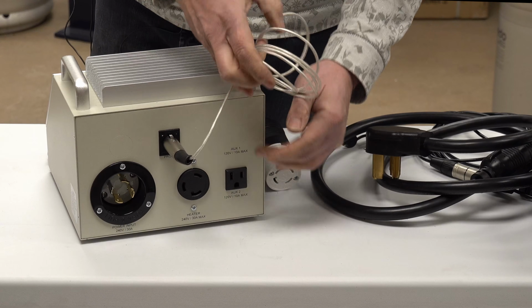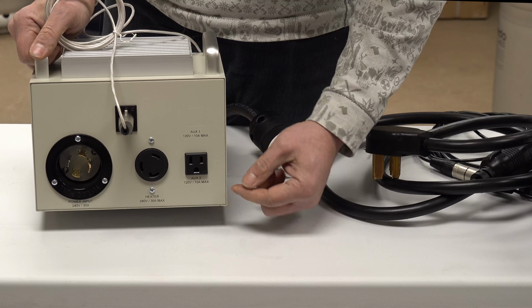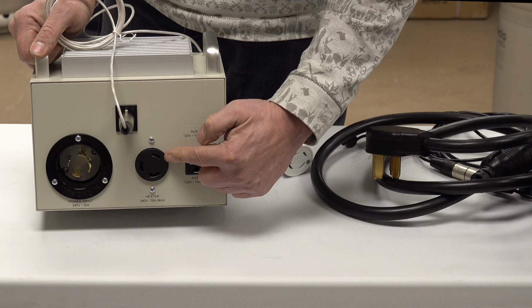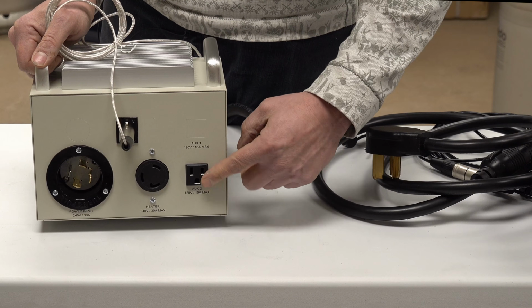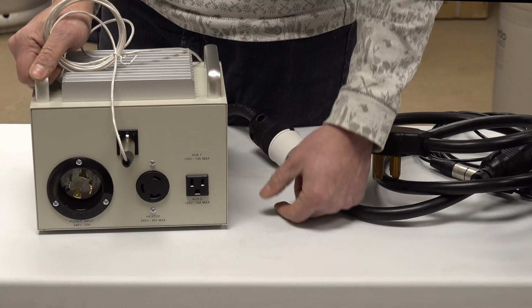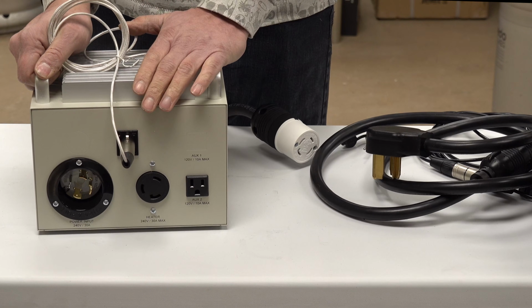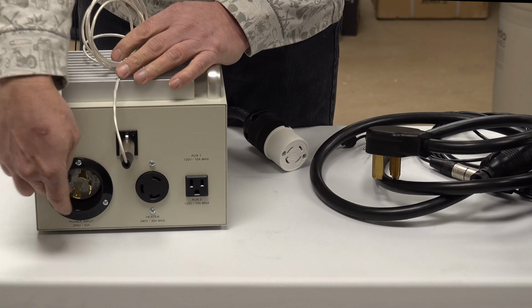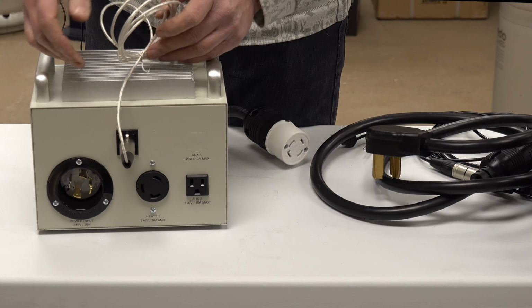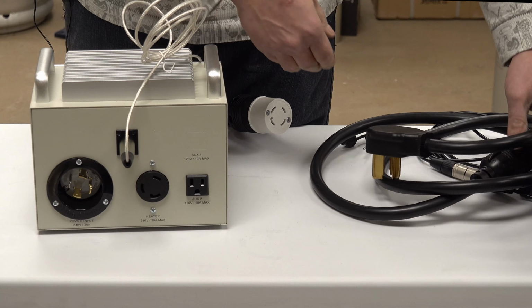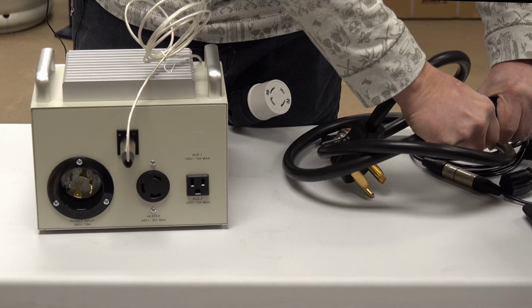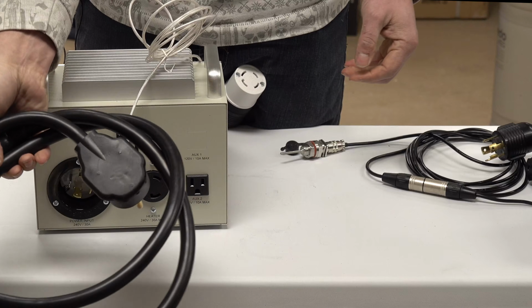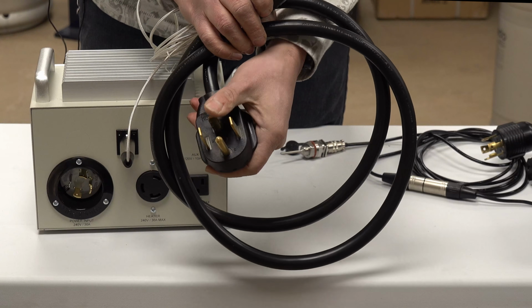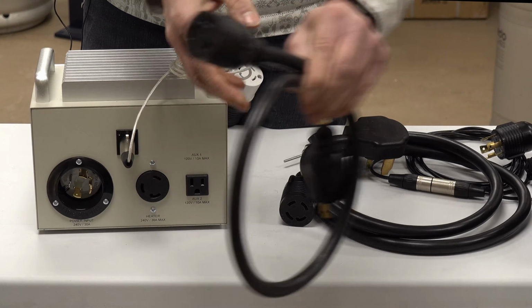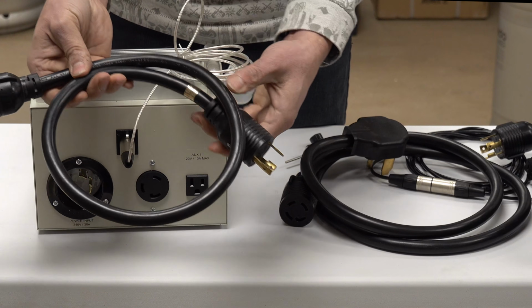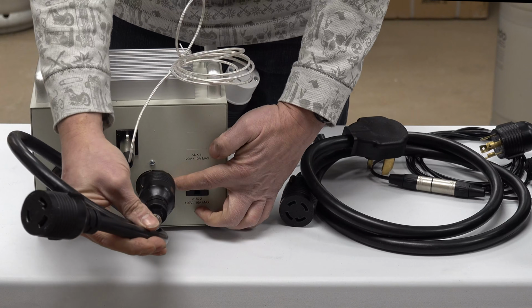And the outputs are the same as the Solo as well. You have an L6-30 for the element output and just a NEMA 5-15 standard 120 volt receptacle on the back for your pump. The Auber Cube does not come with a power input cable or an element output cable. Those are all separate. So basically you would buy a cable like this one to get the power in, right? So your 4-prong in, and then you would buy whatever L6-30 extension cord length you would need to go from this controller here to the element.